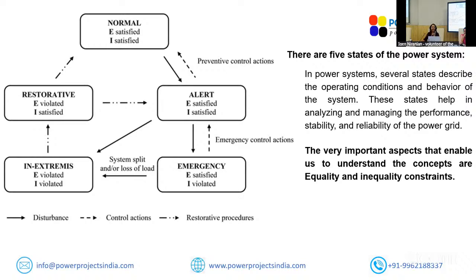In normal, I have two transformers, each only 50% loaded. But in alert, I have one transformer at 100% loaded. If that transformer fails, what is my state? My state is blackout. So alert is without contingency, normal is with contingency, but both look the same otherwise.